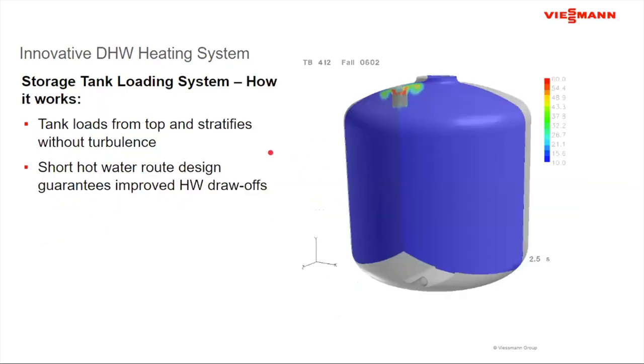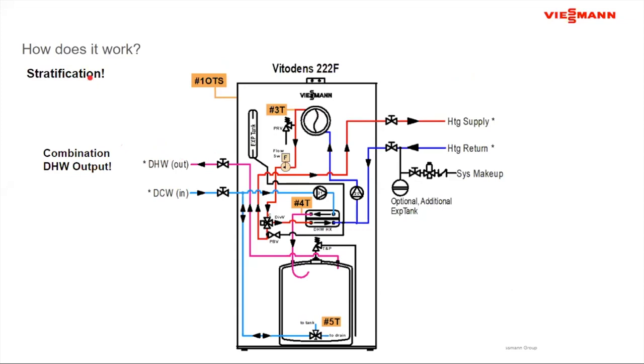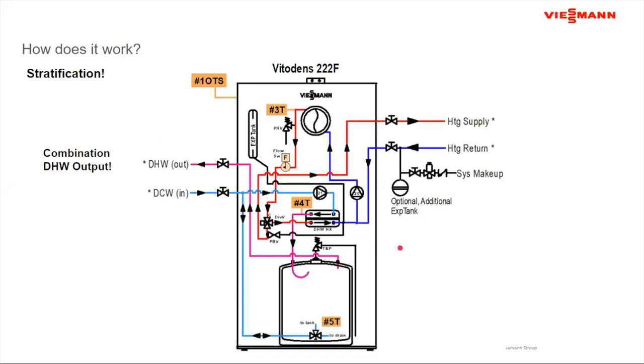What's unique about this is that the hot water is coming into the top of the tank, and it's all about stratification. We bring the water in and load the tank from the top to the bottom when the boiler is running into domestic hot water load. The outlet to domestic hot water is up here as well, which gives me great performance. If I stratify the tank, the hot water from the hot water generation comes into the top of the tank, which I'm drawing against.